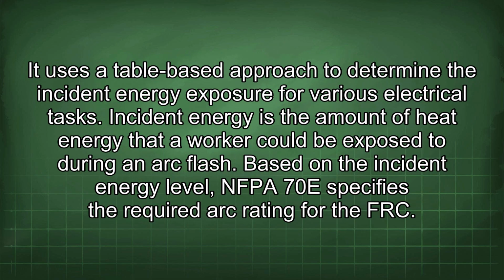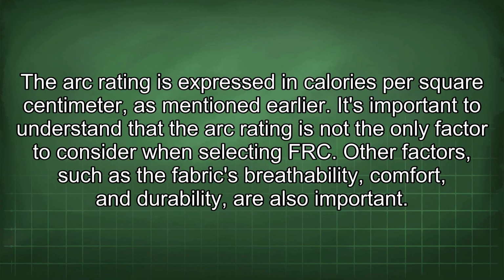It uses a table-based approach to determine the incident energy exposure for various electrical tasks. Incident energy is the amount of heat energy that a worker could be exposed to during an arc flash. Based on the incident energy level, NFPA 70E specifies the required arc rating for the FRC. The arc rating is expressed in calories per square centimeter, as mentioned earlier.